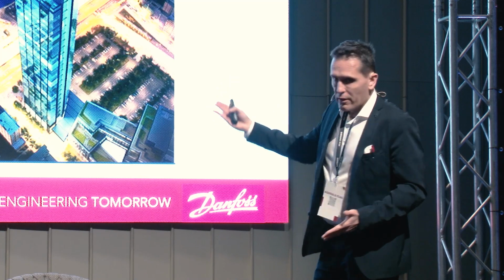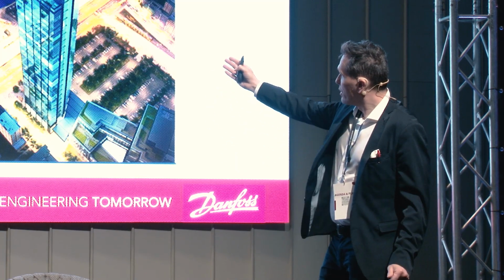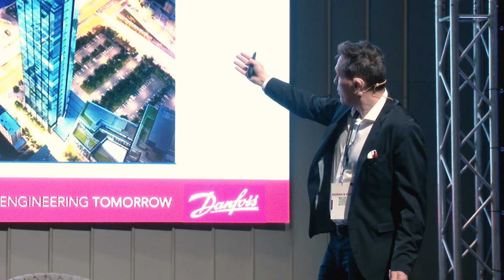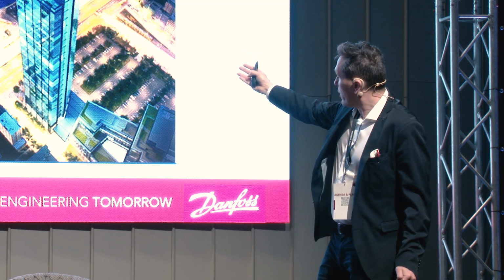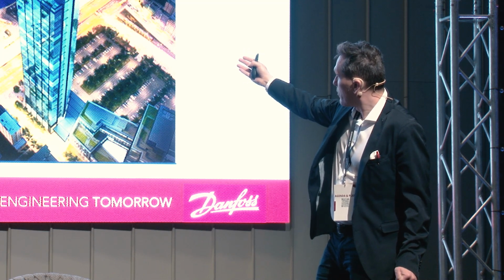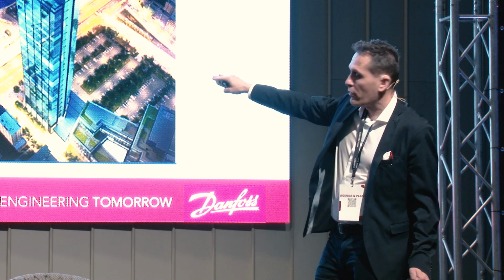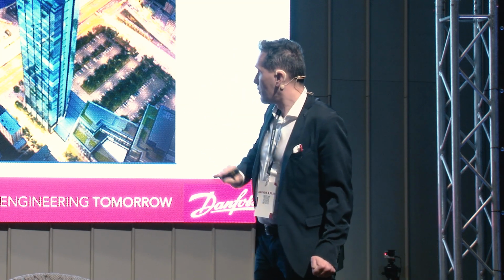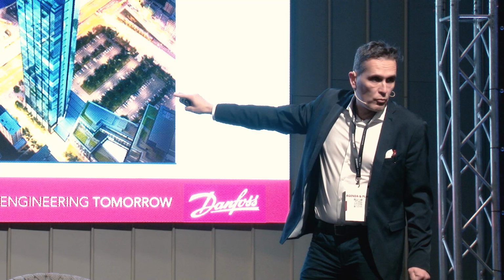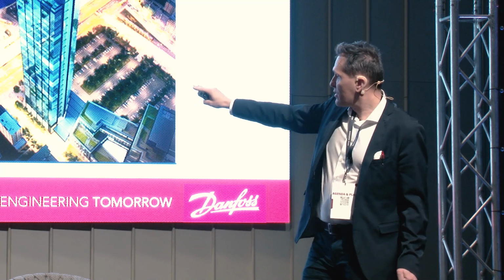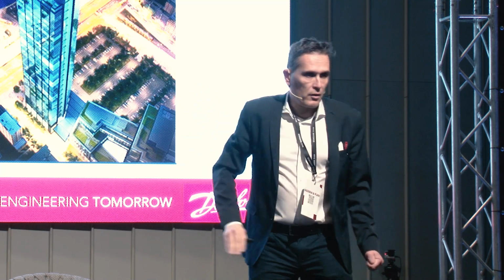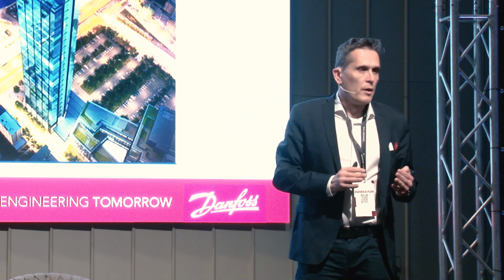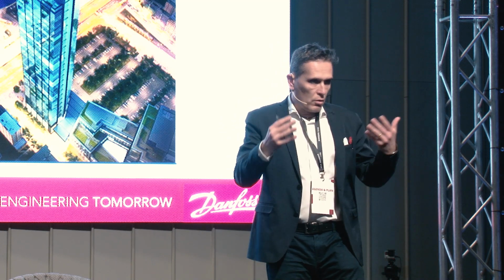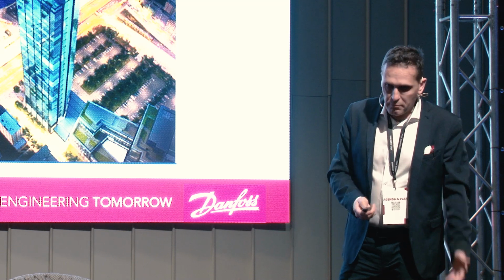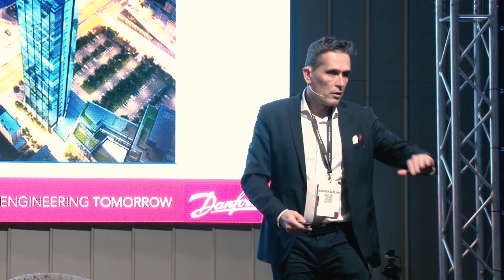And also the Bulgarian standard at 28 meters says the minimum fire resistance barrier should be 60 minutes, but with an extinguishing system, 30 minutes - half. If the building is higher than 28 meters, it says 90 minutes, but with an extinguishing system you can reduce it. So I don't know your local fire code, but maybe this will generate some discussion. You can have questions after.